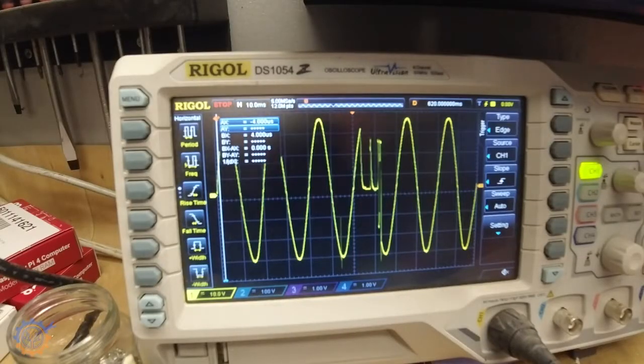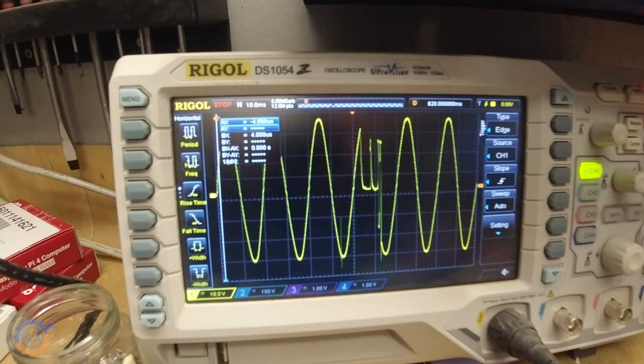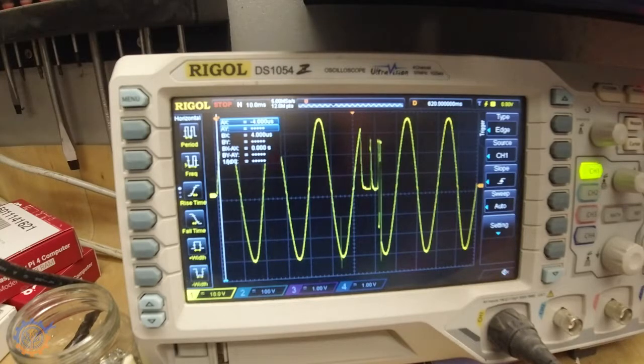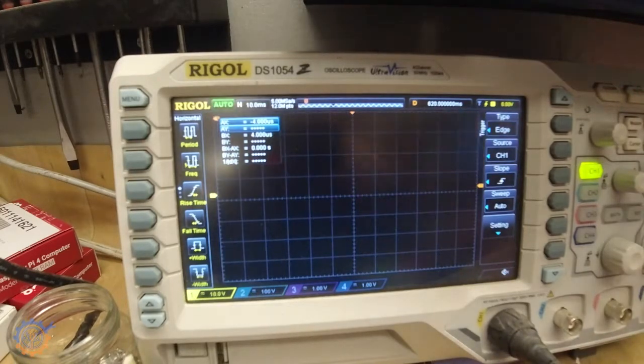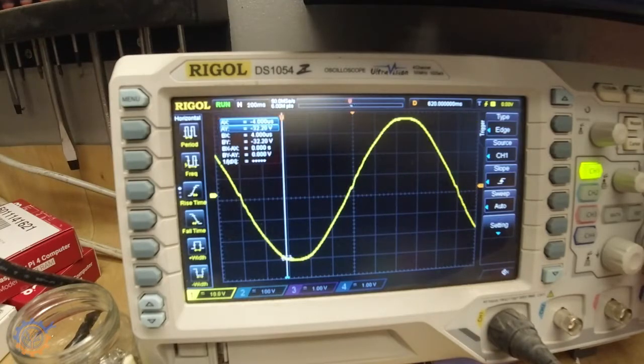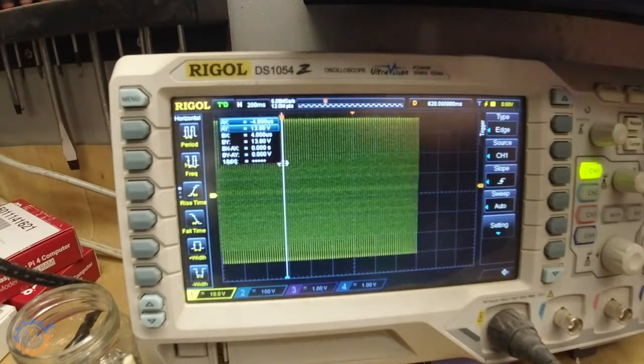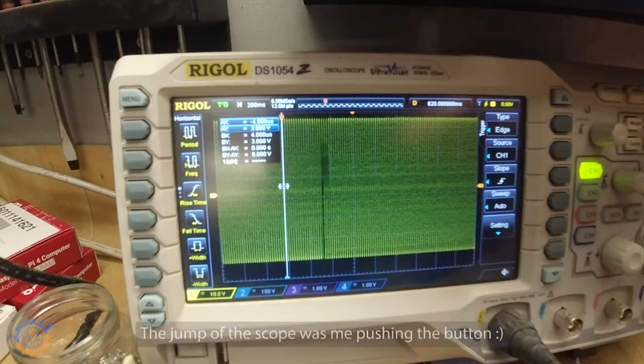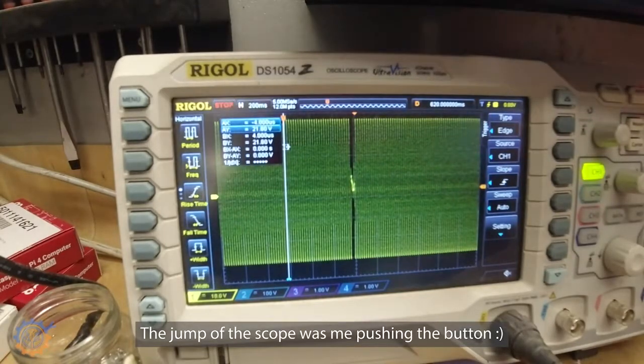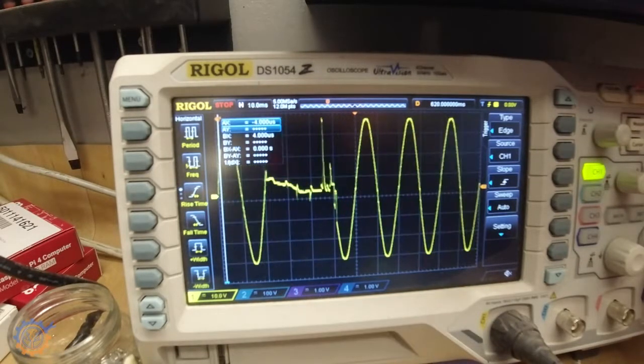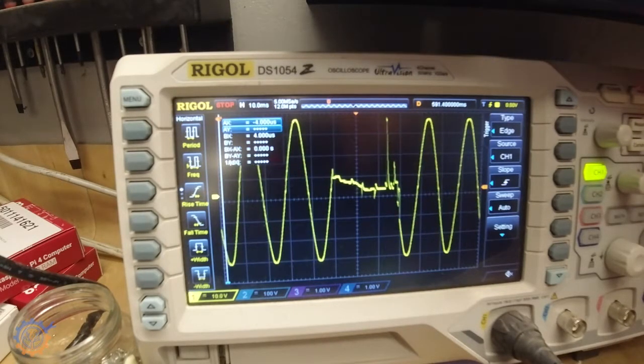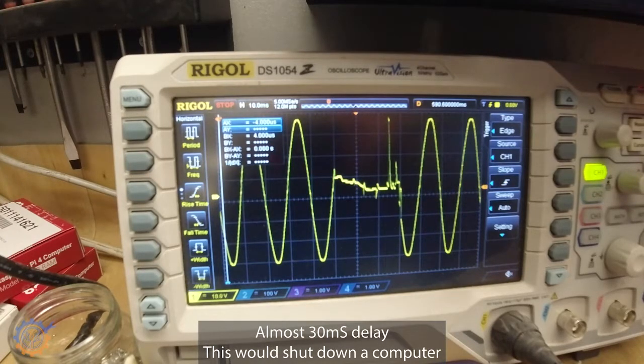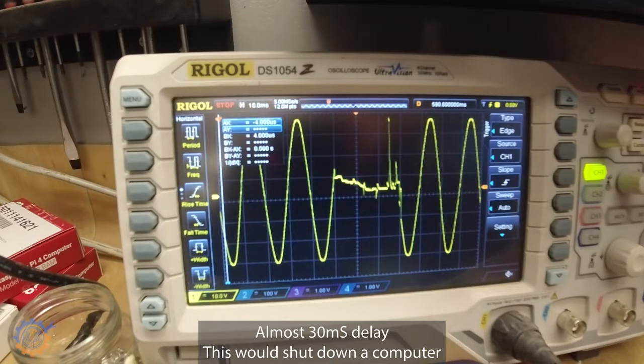Let's hook up the oscilloscope and test it out. So basically here we have one of the triggers I did. This is how it looks like. You can clearly see that depending on how it works it will cause an outage of, in this case, 15 milliseconds roughly. So let's re-trigger this again and see how it works. Let's zoom out a little bit so we can get it on. So basically there we have trigger again. Let's zoom in. And this is even worse. Every box there is 10 milliseconds. And here we have 30 milliseconds where it has no correct voltage.